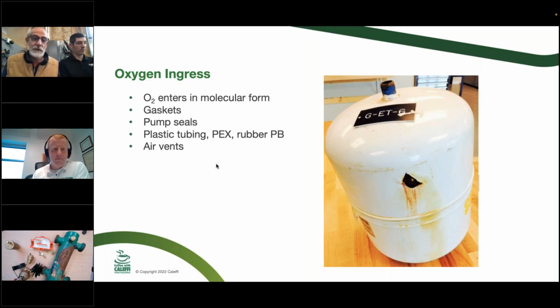I know it happens forever, so maybe it's not a huge deal, but certainly you want to do it where you've got a lot of dirt and debris in the system. Just avoid that potential problem. Yeah, and in those scenarios, if you've got a good dirt separator before the boiler, how much dirt and debris should be at that air separator? It should be pretty much next to none, hopefully. So a Y strainer, any type of device that's getting that deposit before it gets through your pump and your boiler into your expansion tank, which I think is next.